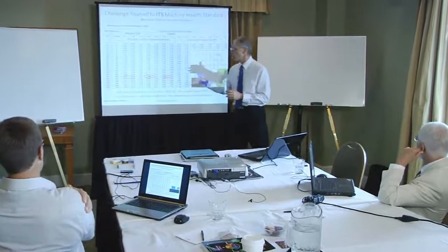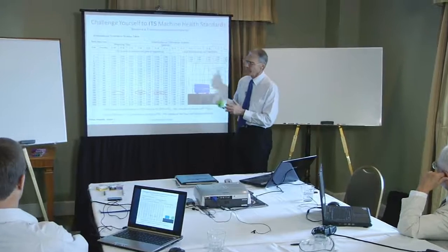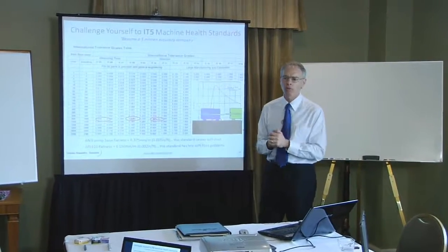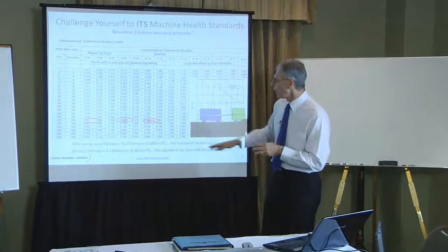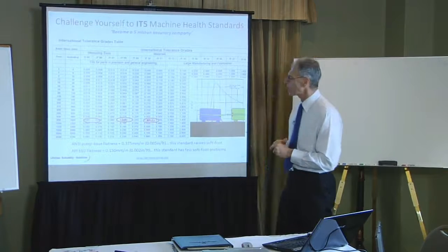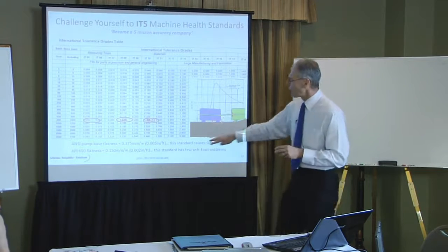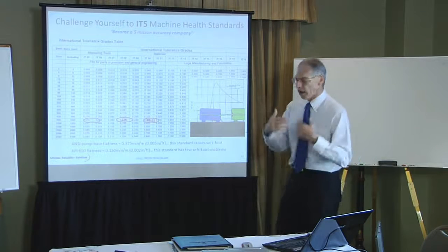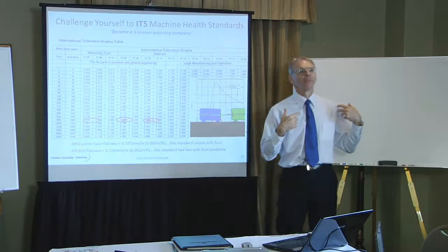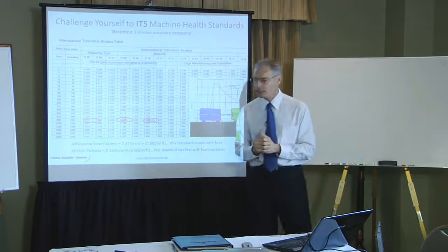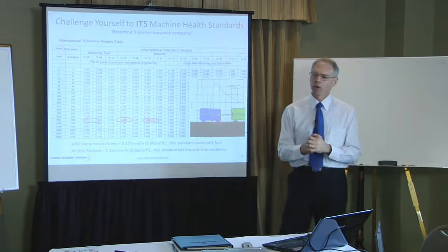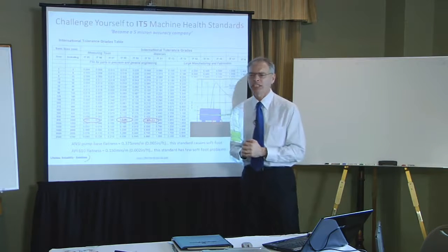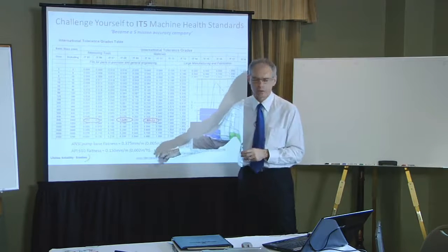Oil and gas guys have gone a step further and said, well, that's not good enough for us. We want to get something that's more certain of good reliability. In their requirements, in the API 610 for base plate flatness, they will accept nothing more than 2 thou per foot. Now, I'm a fitter machinist. I used to machine base plates, and I know that 2 thou per foot is not a big stretch. It's much better than 5 thou per foot, but it's not a big stretch. It's still a soft foot issue there.